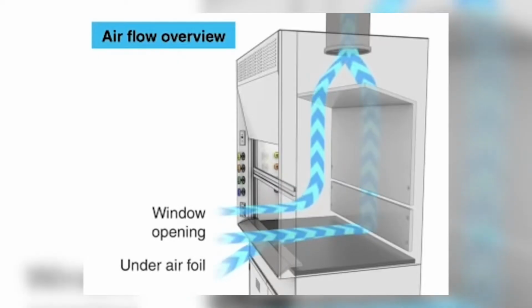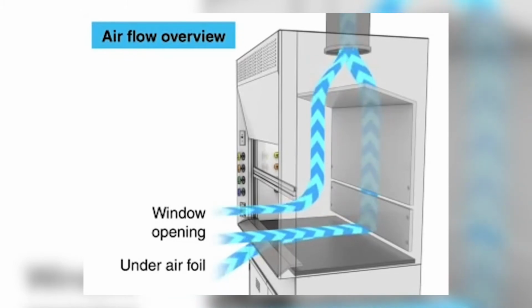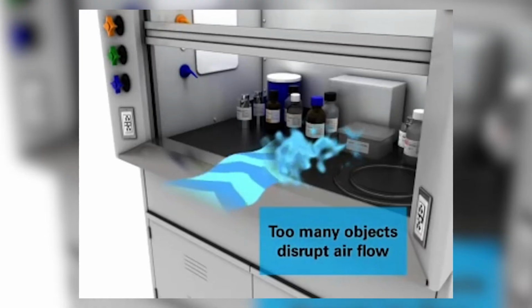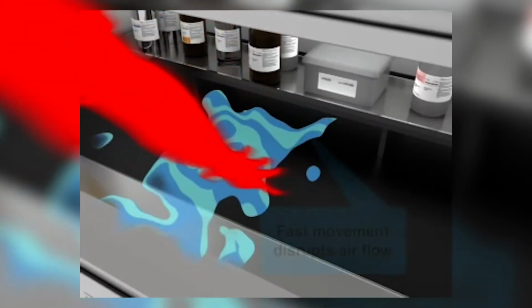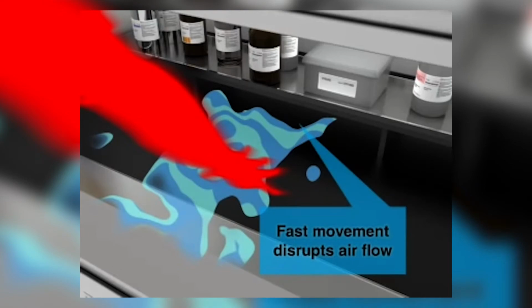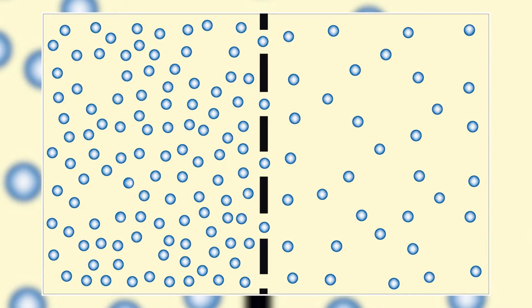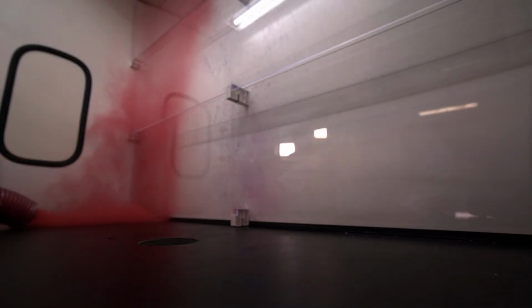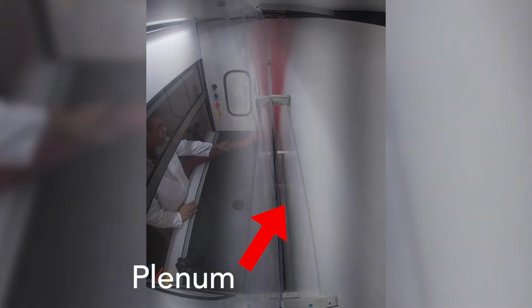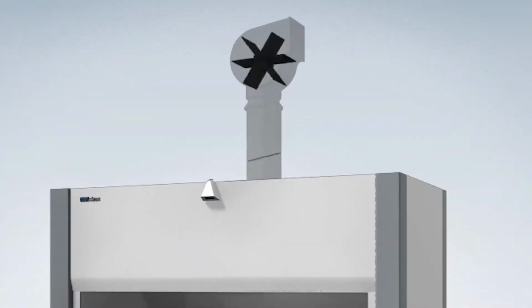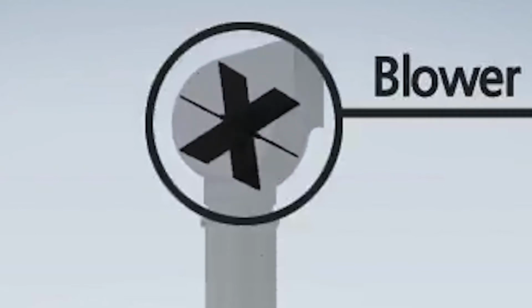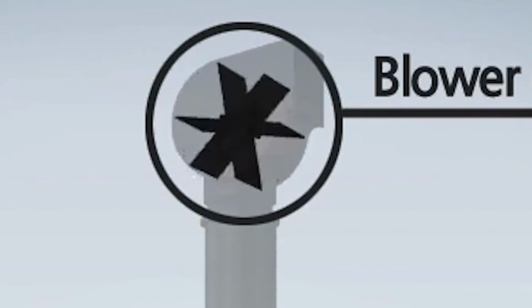Mechanical ventilation and fume hood performance are anything but simple, but having a general understanding of what the air is doing allows you to do things that will make the hood work better, and to spot things that may be impacting its performance that need attention by the facilities or maintenance people. Just like water running downhill, air flows from high pressure areas to low pressure areas. In a fume hood, the low pressure area is the plenum. The plenum is the space between the baffles and the back wall. There is an opening at the top of the plenum where the ductwork is attached. Then there's a fan, usually on the roof, that creates the lowest pressure for the entire system. You could say that the fan is sucking the air through the hood.